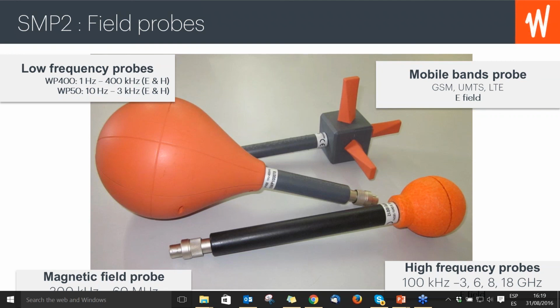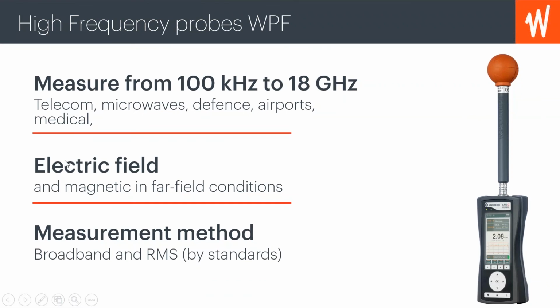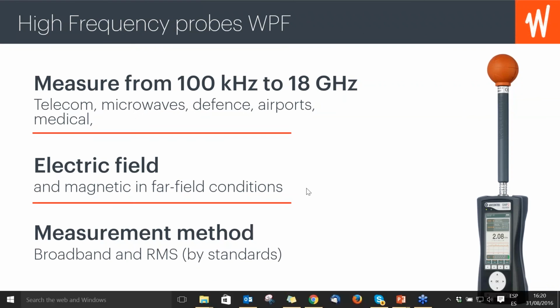And we have two probes for measuring low frequency, the WP50, which covers from 10 hertz till 3 kilohertz, and it's for both electric and magnetic field, because in low frequency usually we are in near field conditions, and in that case the electric field and magnetic field have to be measured separately. We have also the WP400 probe, which is state-of-the-art of what we have at WaveControl. We have had it since the end of 2014. It covers from 1 hertz to 400 kilohertz for both electric and magnetic field, but it's a selective probe, which means that you can do several kinds of measurements, not just broadband measurement using this probe.